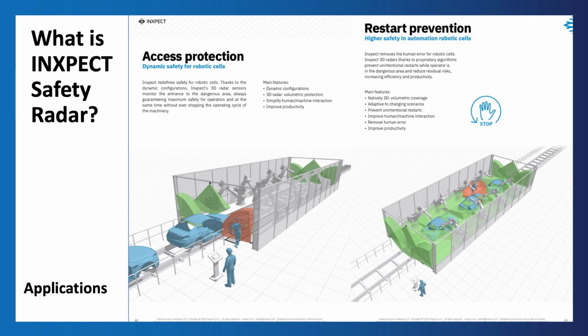Or if you have it in a safe manual restart mode, it's going to wait for that 4 seconds of no detection. You can monitor by Modbus or through a digital output, send a signal that, hey, we're good to go, have an indication light, and then have a manual reset input. So that's a safe manual system that you're operating in.